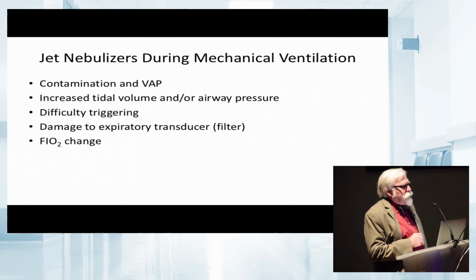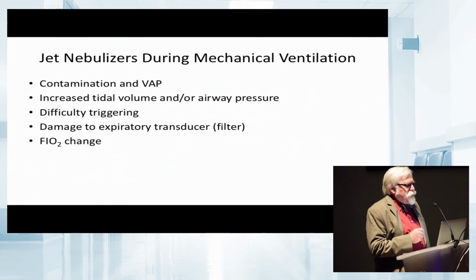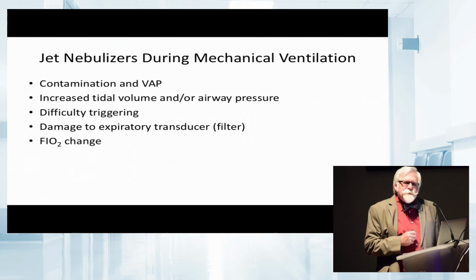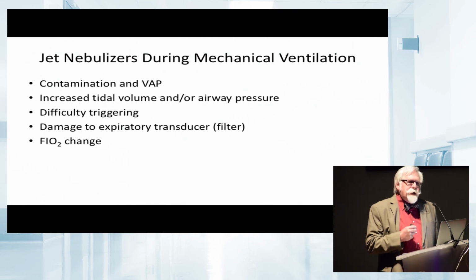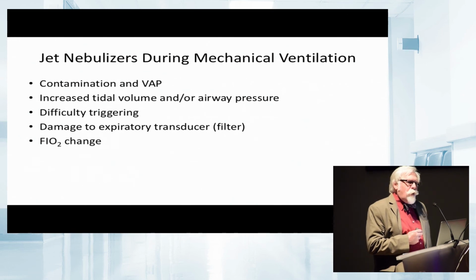It's also important to appreciate that there are a number of potential problems with the use of jet nebulizers during mechanical ventilation. With a jet nebulizer, it's easy to contaminate the ventilator circuit and then contaminate the lower respiratory tract of the patient, and in that way be a cause of a ventilator-associated pneumonia.